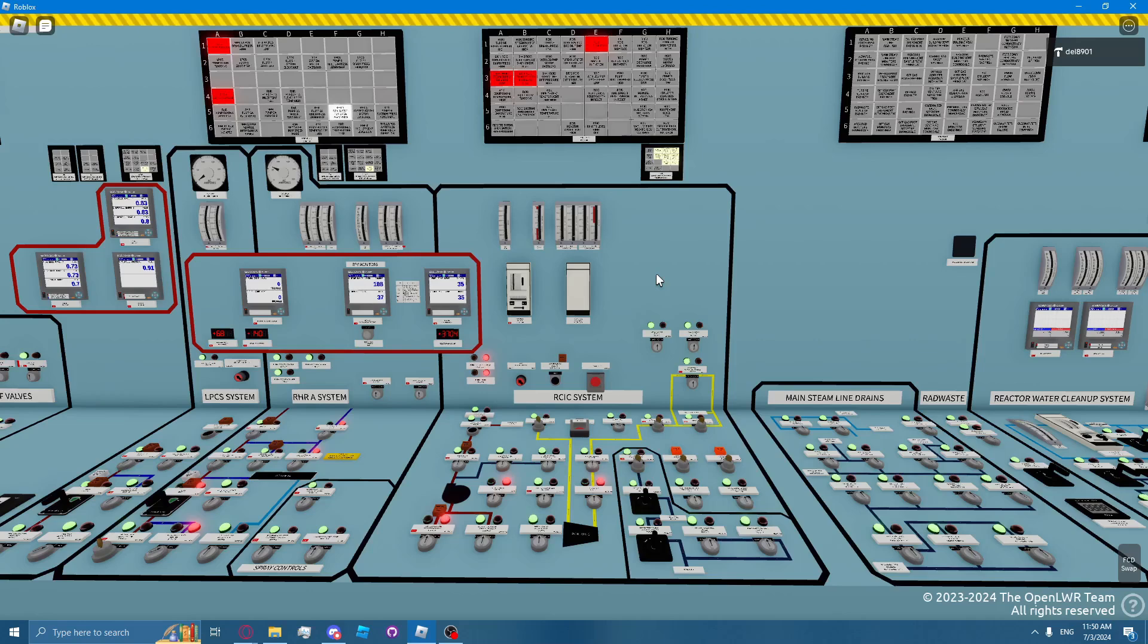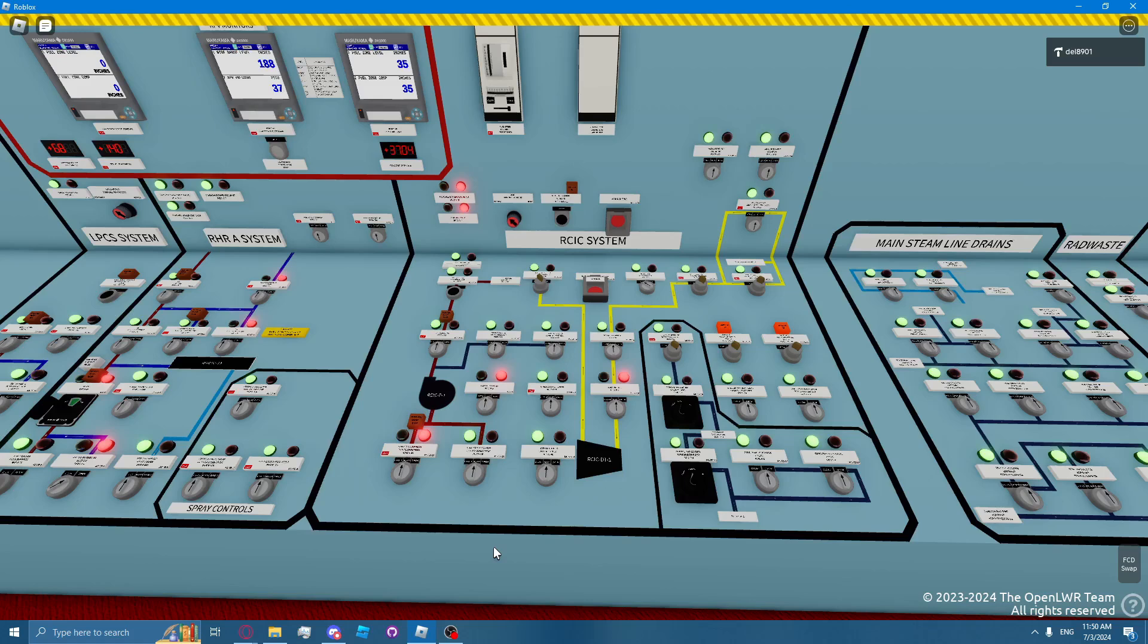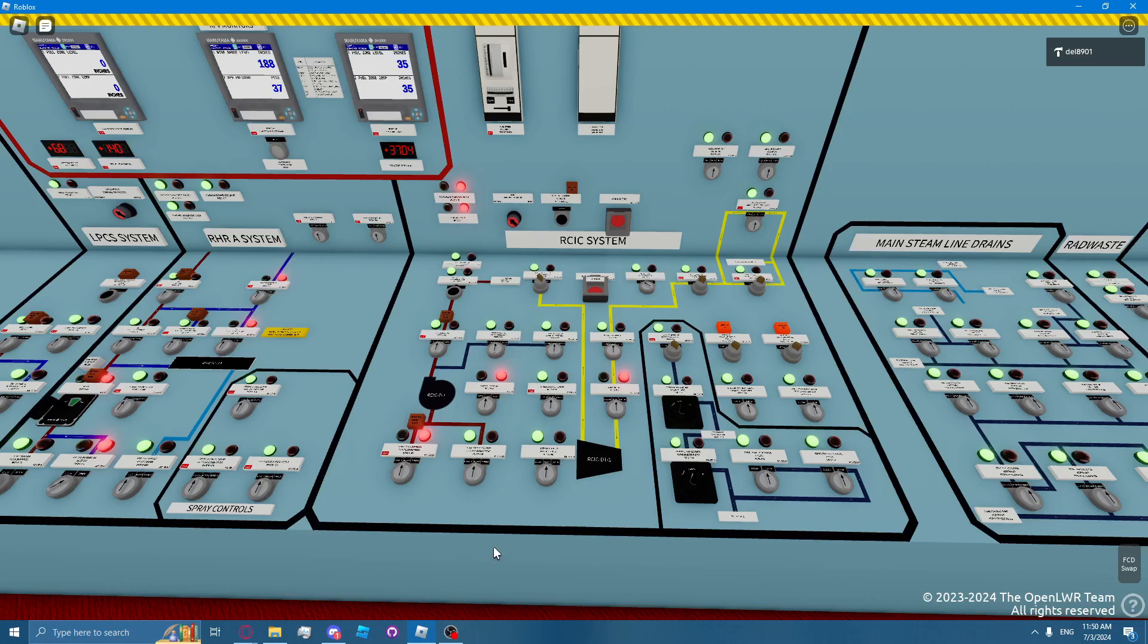The RCIC system can be operated in the CST-to-CST mode, or more commonly known as the tank-to-tank mode, where they line up the CST suction to the CST discharge, which allows for flow testing or reducing reactor pressure by using reactor steam. The RCIC system can also be operated in the Suppression Pool-to-CST mode, and it can also be operated in the RPV injection mode.